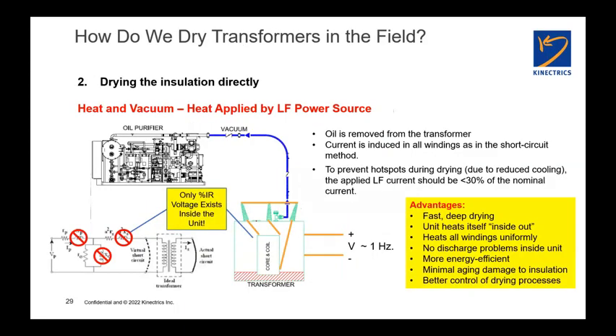Lastly, you can try and dry the insulation directly. And in the factory, that can be done using something called a vapor phase dryout system. I'm not going to get into that because we could spend a morning or an afternoon just talking about vapor phase. But I'm going to talk a little bit about low frequency heating. In a low frequency heating system, what we do is we pull the oil out of the transformer. We short out the transformer like we were going to do a heat run or a load loss test, impedance measurement.